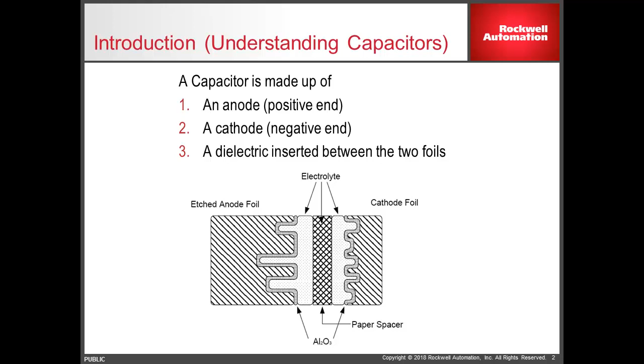After a prolonged period of time with lack of voltage applied to an aluminum electrolytic capacitor, the oxide will start to break down and the leakage current will be very high. Reforming is the process of regrowing the oxide in the grooves of the aluminum foil so that the capacitor will not fail.